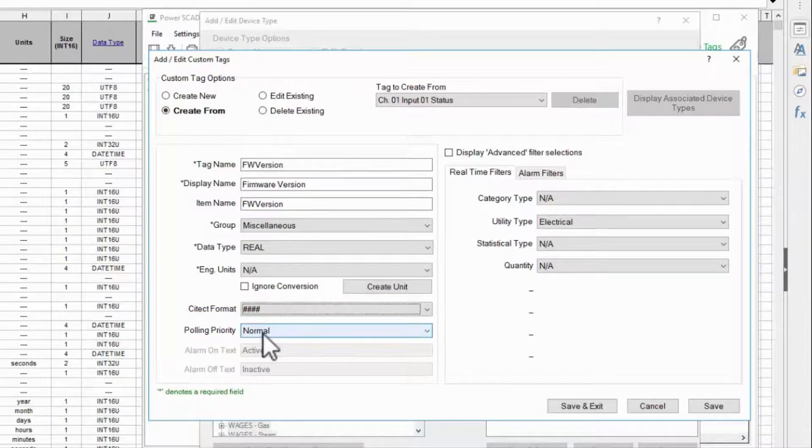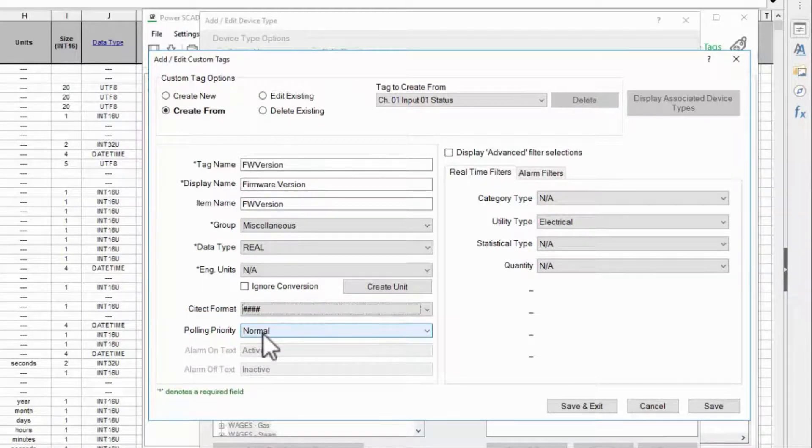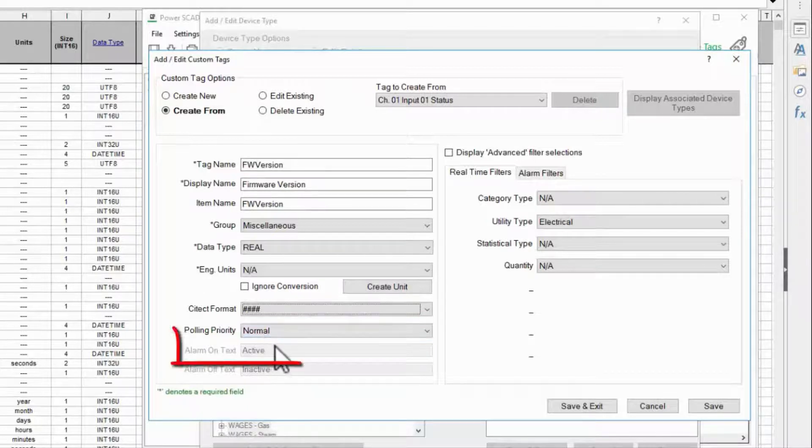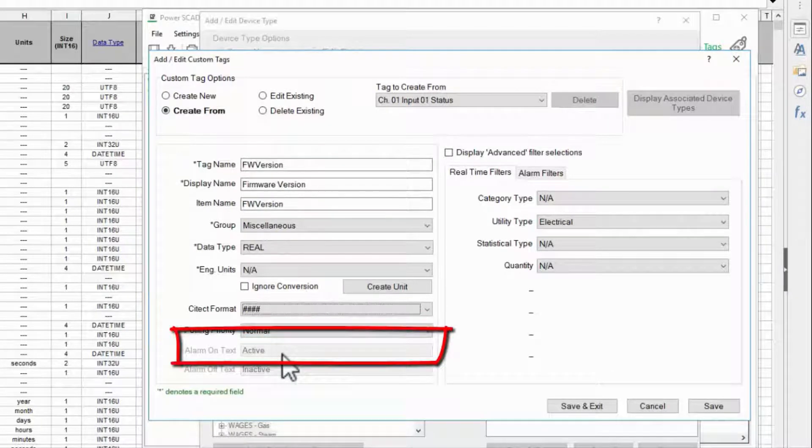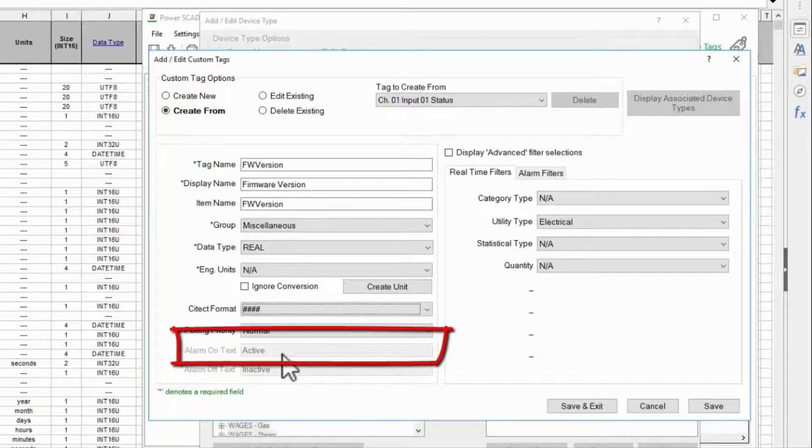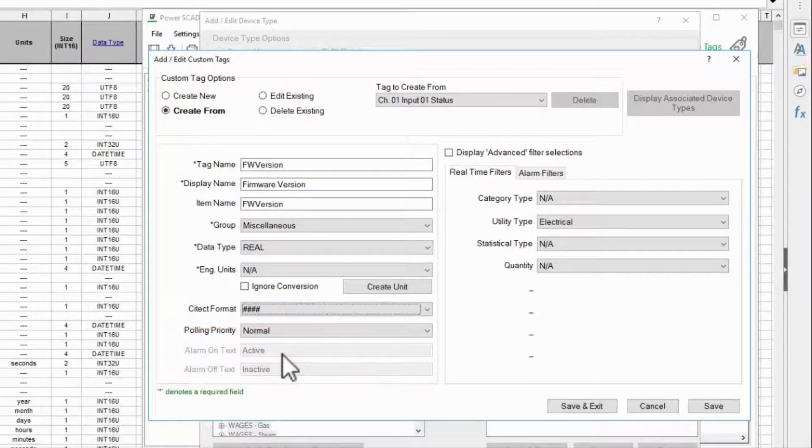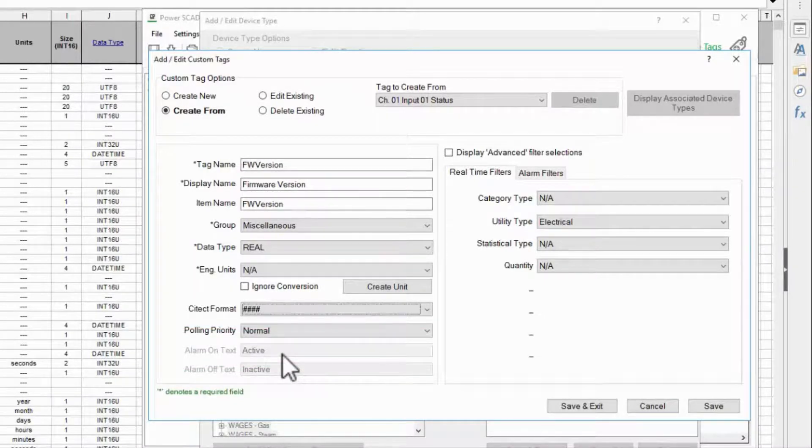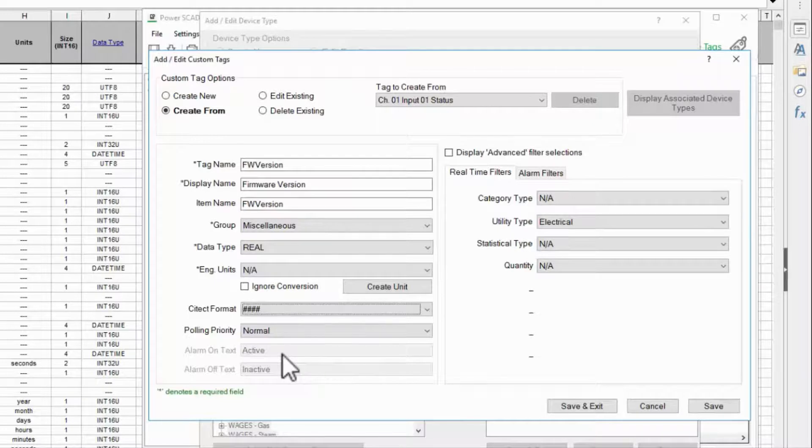Polling priority sets that default priority that we saw when we addressed our other tags. Since it mostly has no effect I'll leave it at normal. Alarm text is used by digital tags only. They display this text on the alarm pages when their alarms trigger, if your profile uses them as alarms.